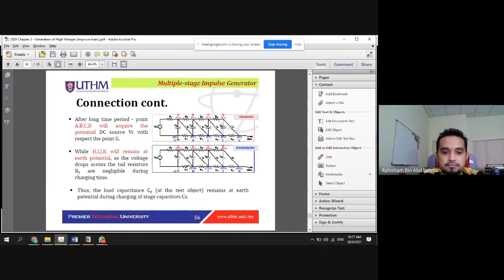This kind of uncertainty is why any testing related to the impulse generator requires testing for more than 20 times to obtain the average value. It means that we charge the capacitor, then discharge, pump, and generate. For example, 400 kV, 300 kV, then the other one 350, the other one 370, the other 410. We will have these uncertainties throughout the test. That's why we need at least 20 values to get the average value for this arrangement.